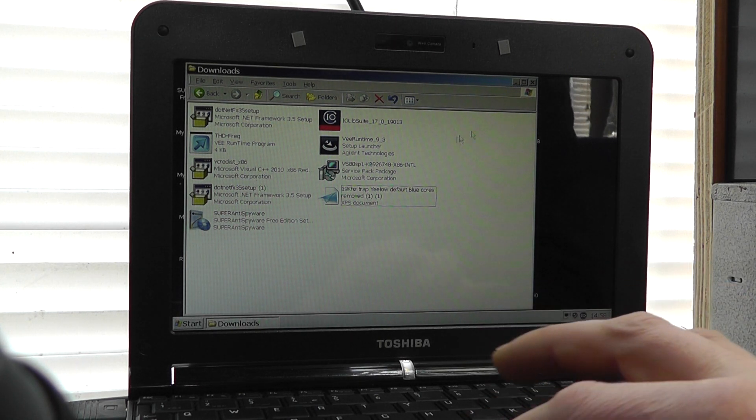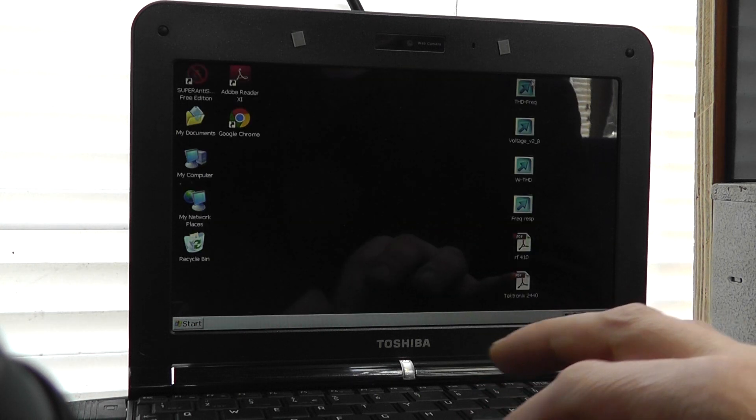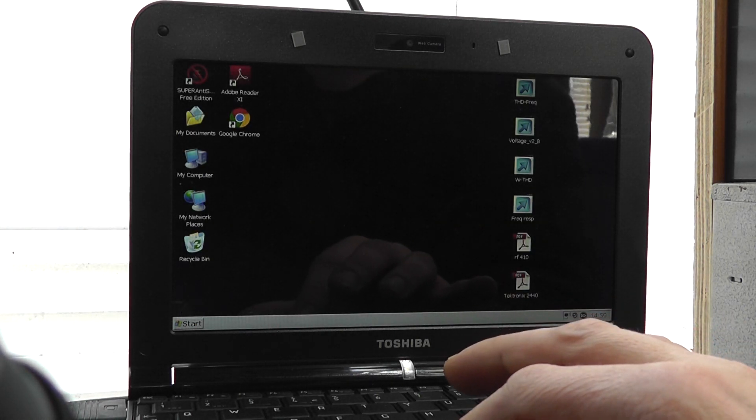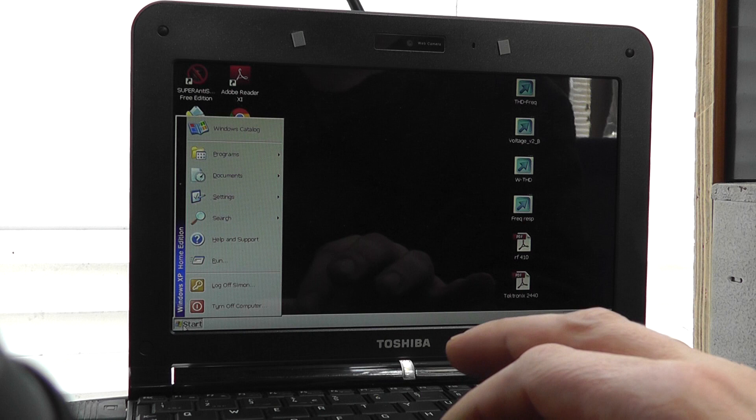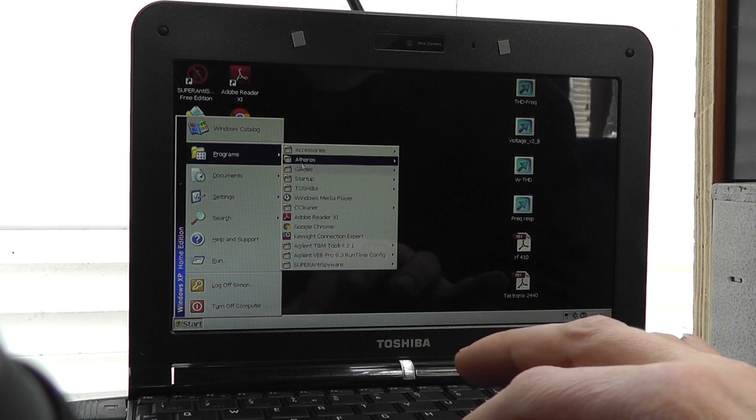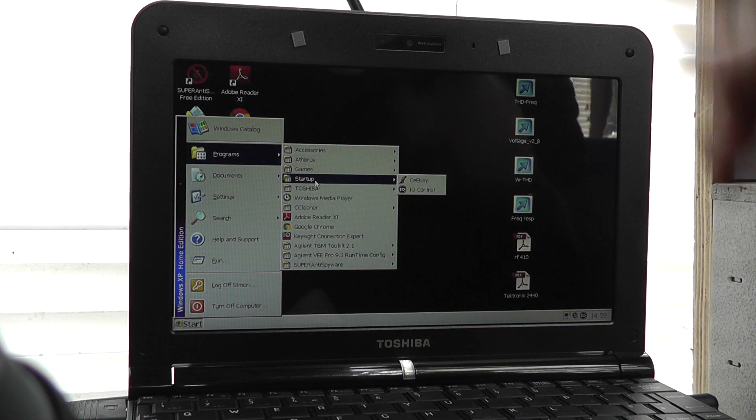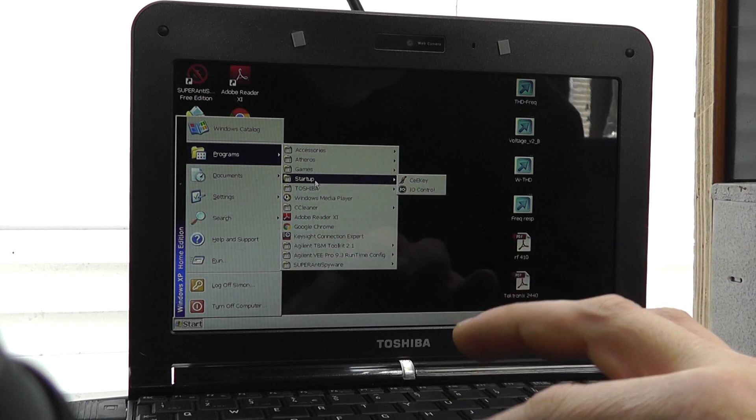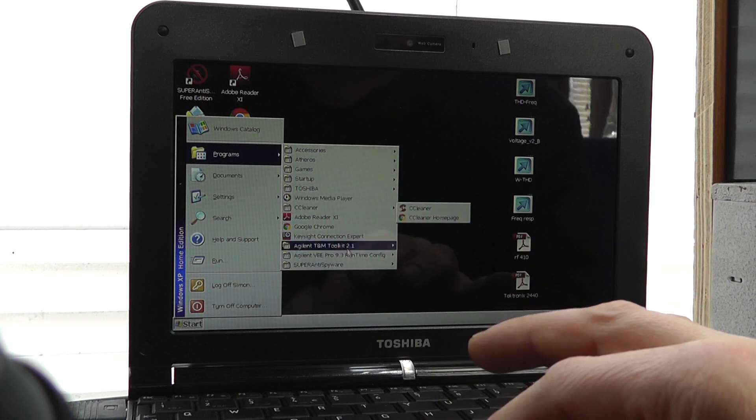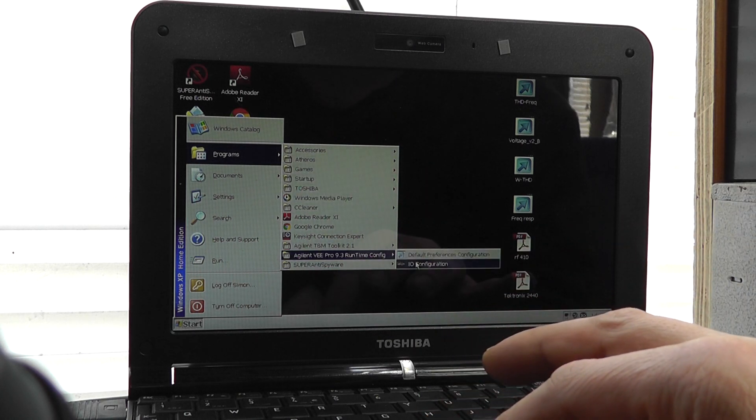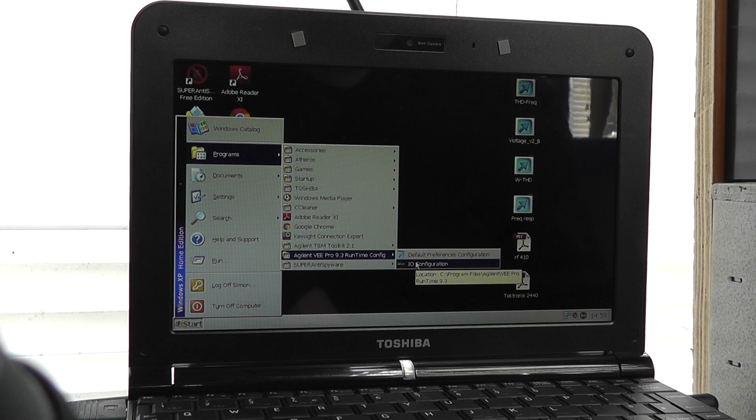Now when you connect up your GPIB adapter, you've got to be absolutely sure that it's been detected by the computer. So when you plug it in, it's actually detecting the device correctly, and it will only do that once you've installed all the software correctly.